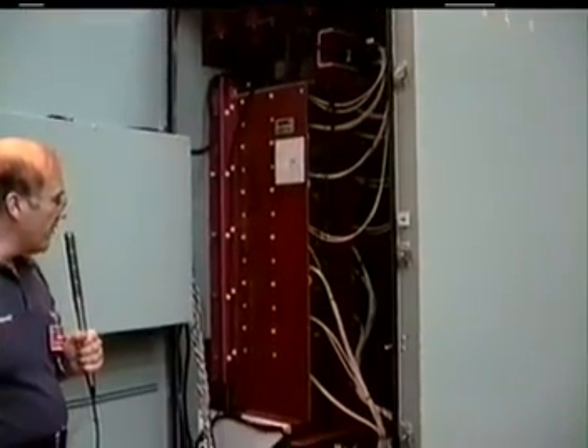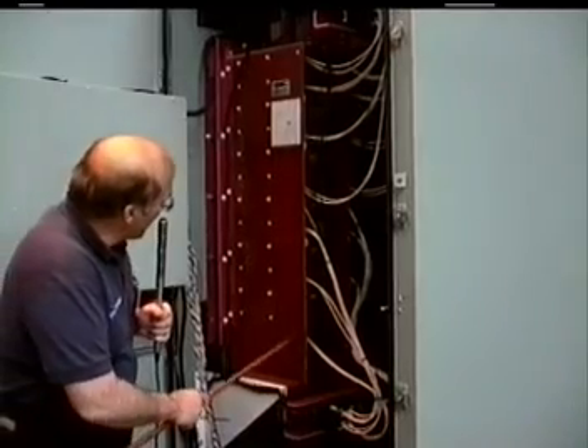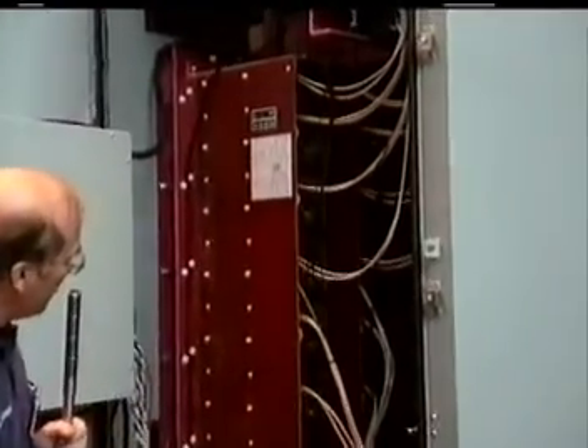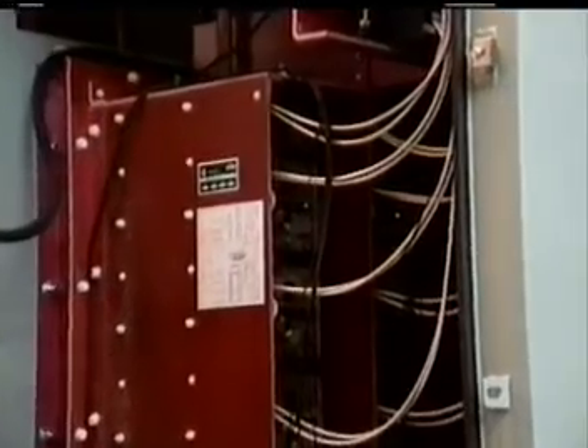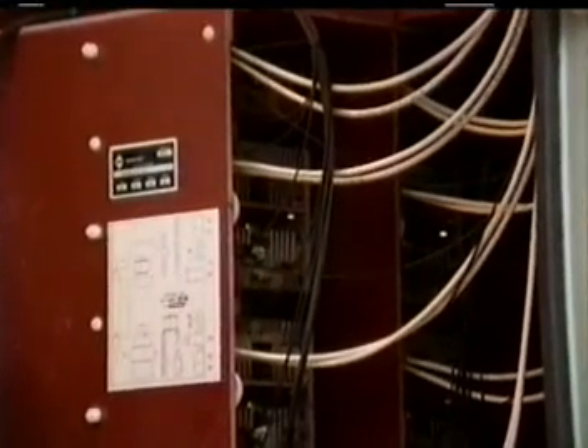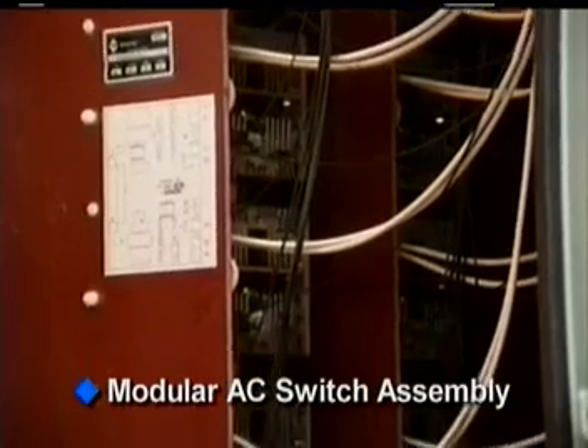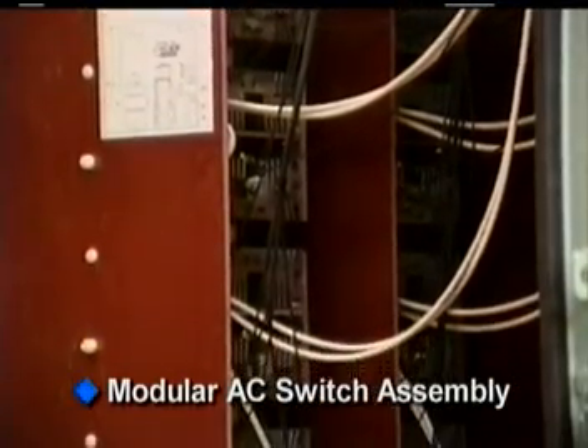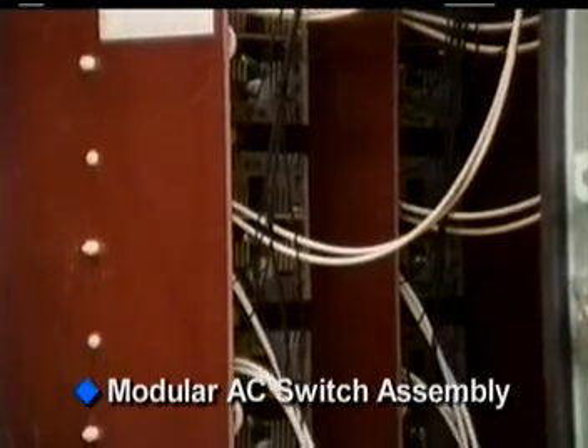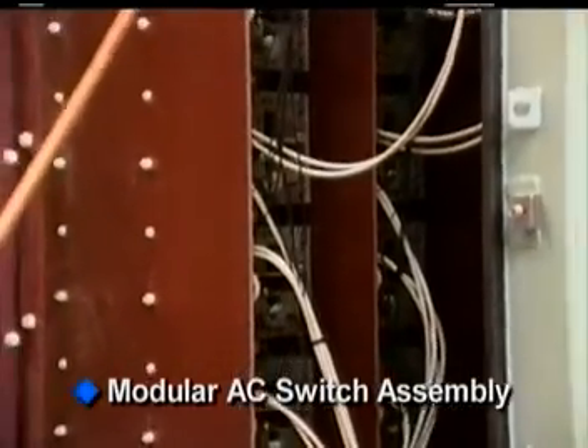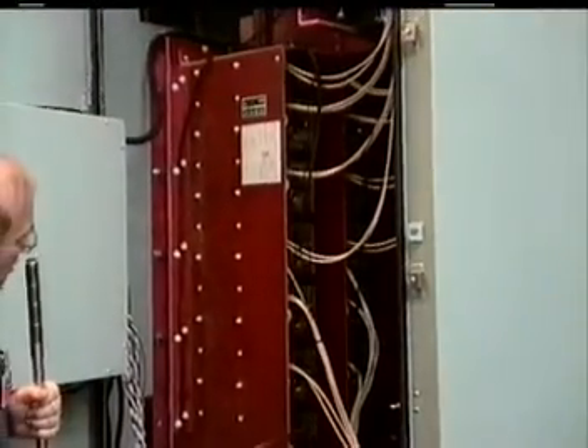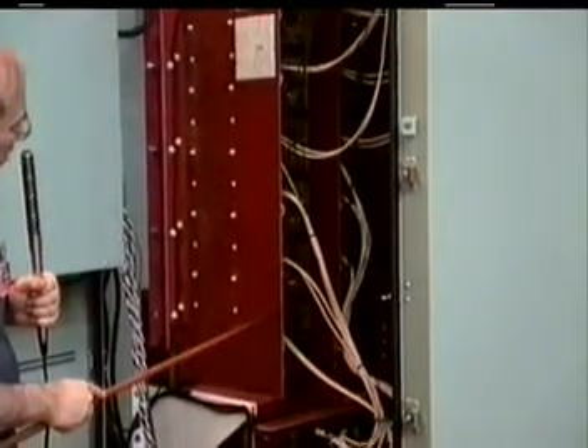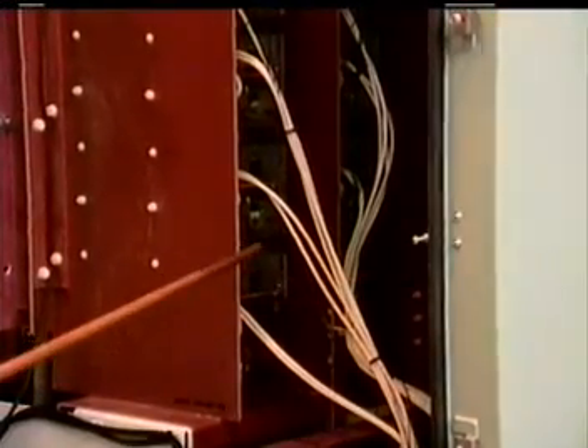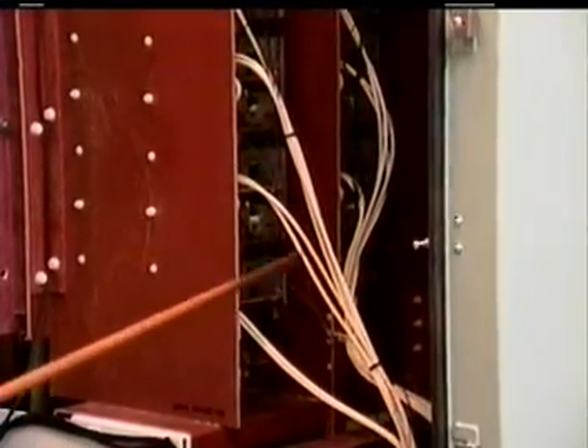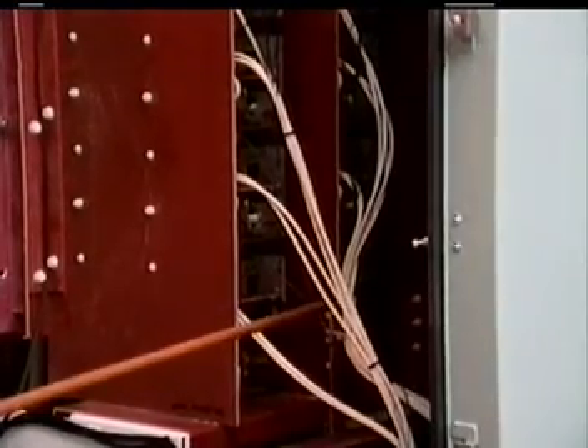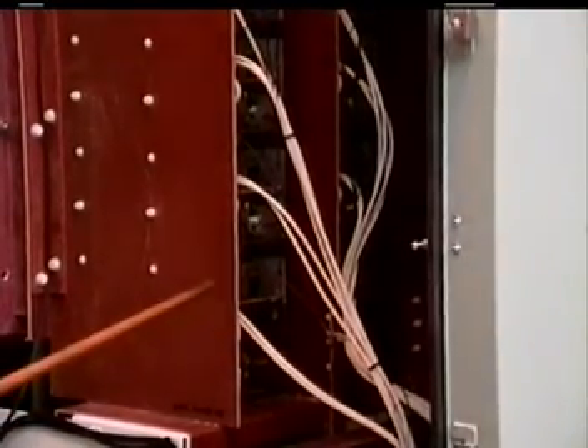This is another view looking from the side to be able to see the actual AC switch cells within the assembly as viewed from the side. The reason these cells are turned on a front to back or a side mount is to provide for easy access from the bus connections coming into the unit and going out of the unit. There is enough space in here to allow for each cell to be extracted from a maintenance viewpoint for inspection or for testing from the built-in self-testing mode of the microprocessor control.